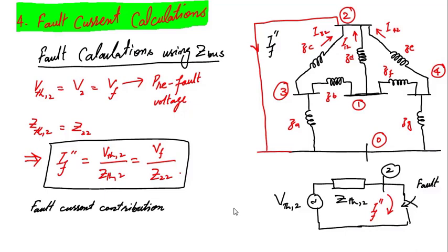After calculating the fault current flowing out of bus 2 into the reference, the next step is to calculate the contributions. We want to know exactly how much is being contributed by the adjacent buses toward that fault. Based upon this current value, we will be able to do the relay settings.